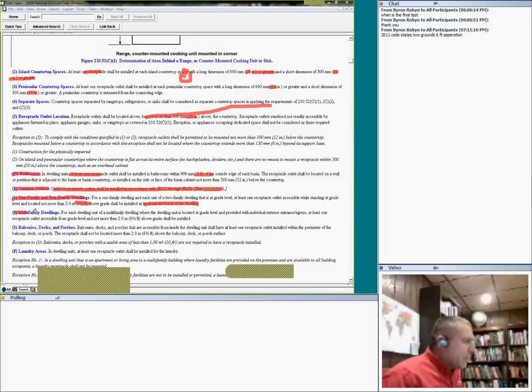Multifamily dwelling, this is really interesting. A lot of people, guys, forget this one. In a multifamily dwelling, you only need it if you have an exterior entrance, at least 1 receptacle outlet from the grade. So if an apartment building has an exterior egress door that opens to the outside, then you need a receptacle, only for the apartments that open directly to the outside.